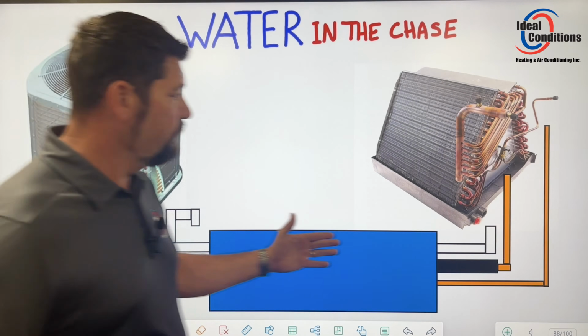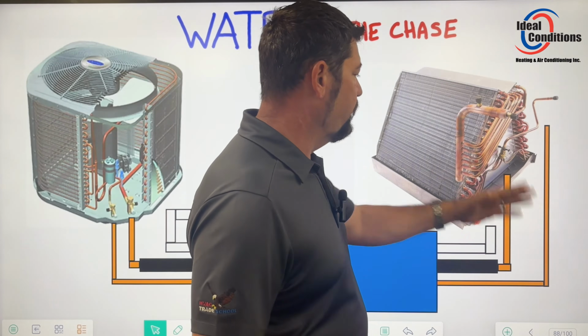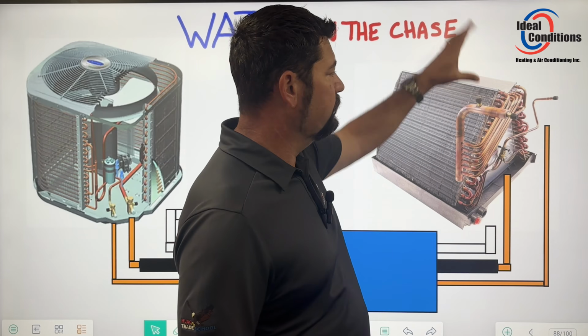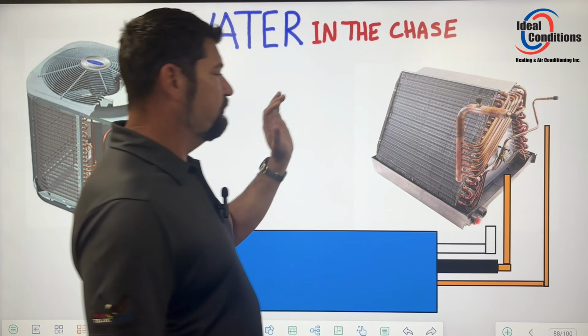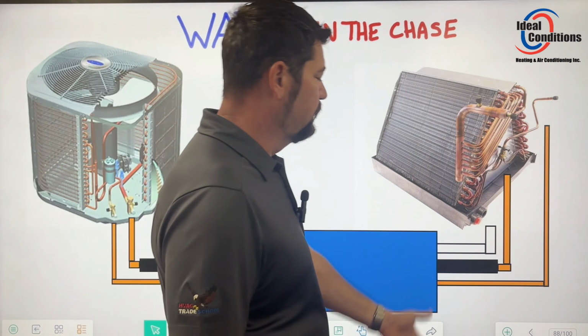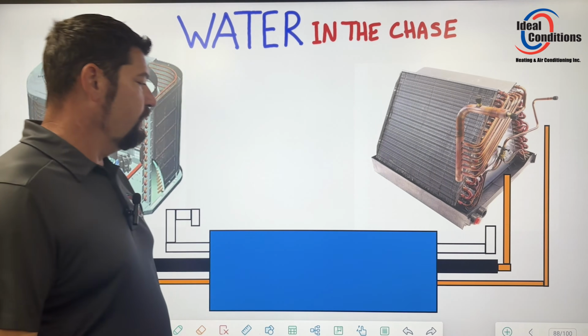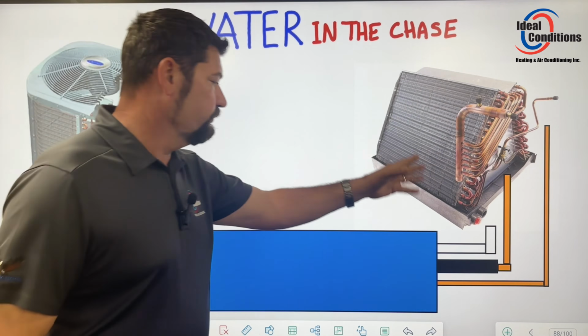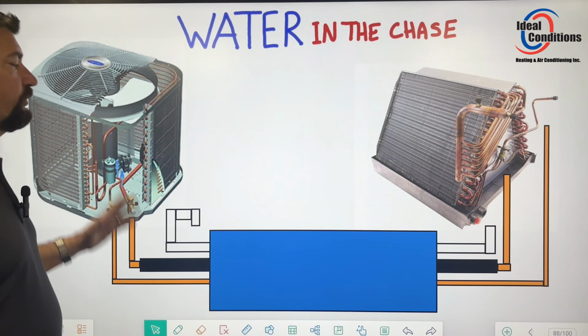Or you might even come in here and go, well, I got a low superheat. Do I have an airflow issue? Is my coil clean? Do I have good air filtration? Am I turning at the right RPMs on my motor? Is my speed correct? Good CFMs? All of that. If all of that checks out, and then you go, man, my superheat just won't change. You're in the right direction, but that doesn't mean that the system is overcharged.